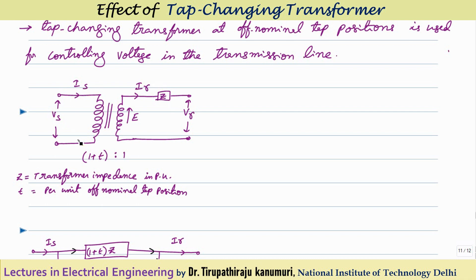Let us take a tap changing transformer represented in a per-unit diagram. Z is the per-unit impedance referred to the secondary side. At the receiving end, the current is Ir, receiving end voltage is VR, and the generated voltage on the secondary side is E. The primary side voltage and current are VS and IS. Because the tappings disturb the nominal ratio, I represent that change by T, where T is the per-unit off-nominal tap position, and Z is the transformer impedance in per unit.